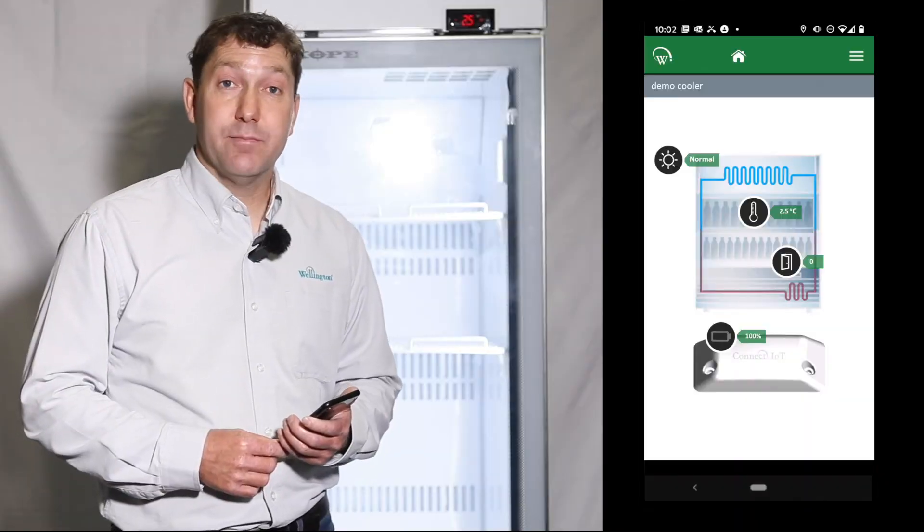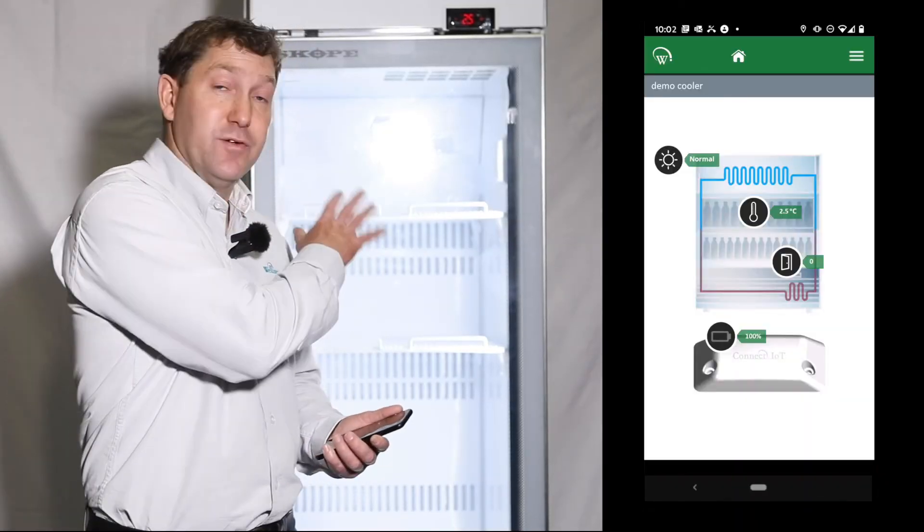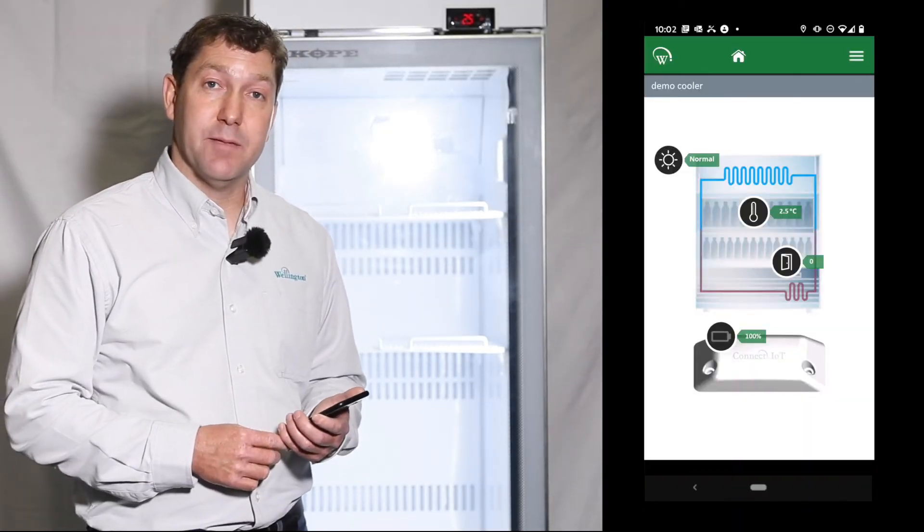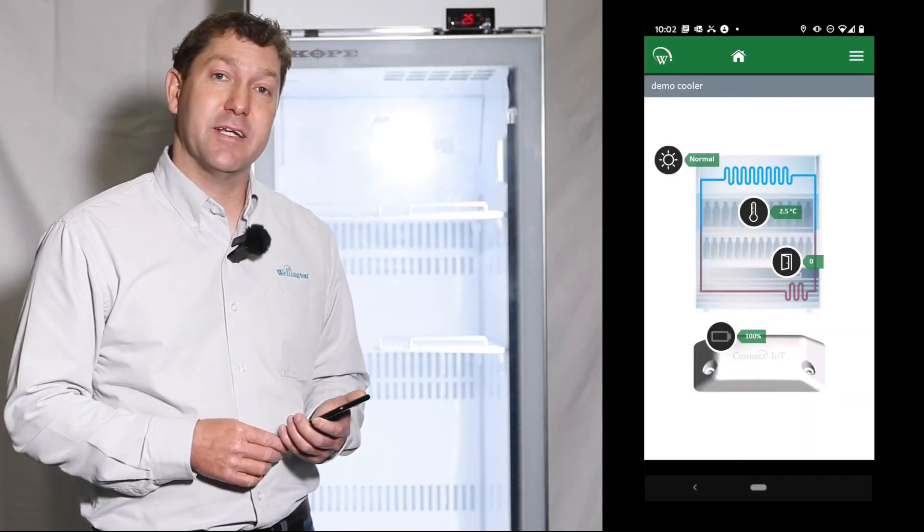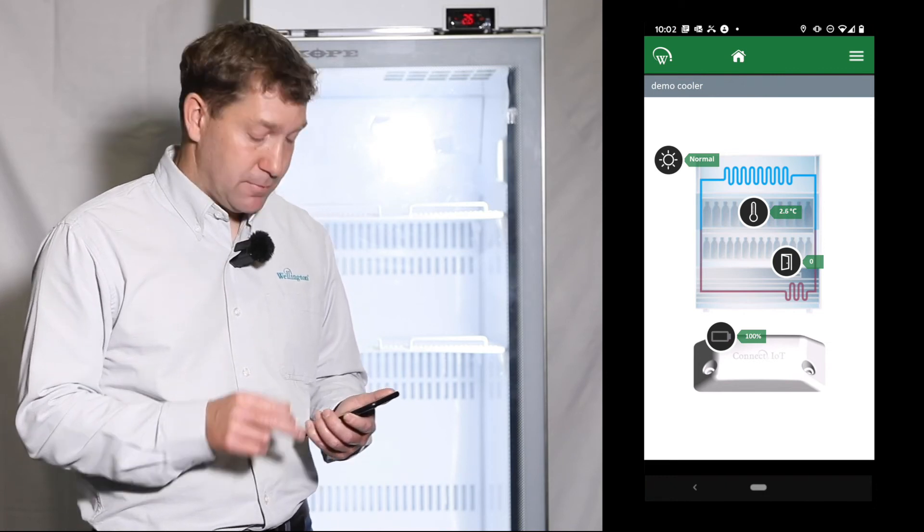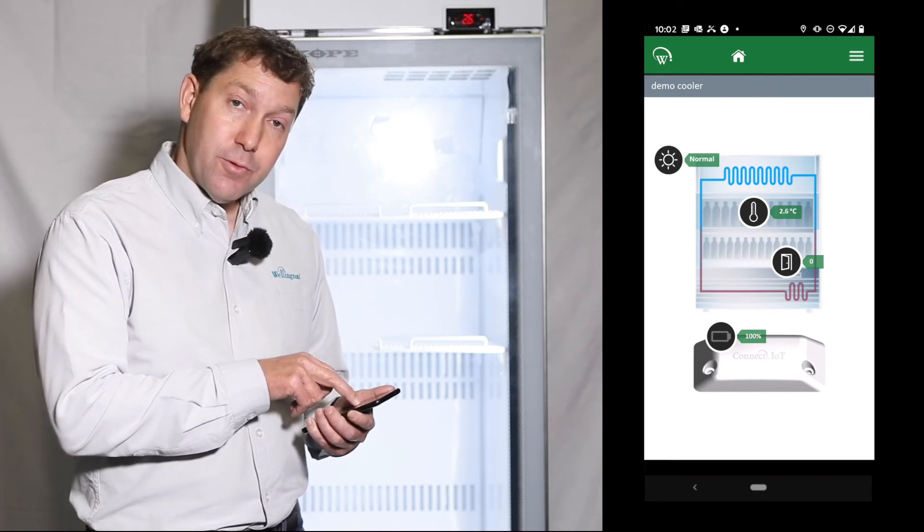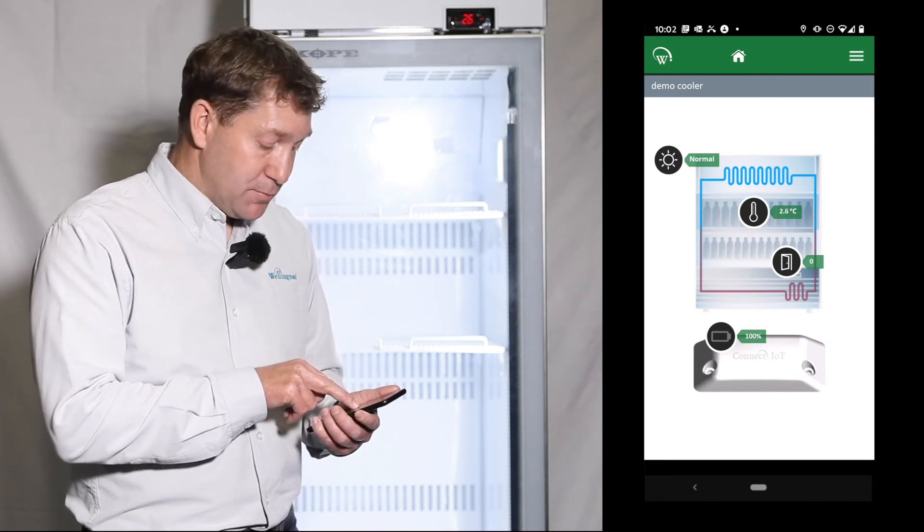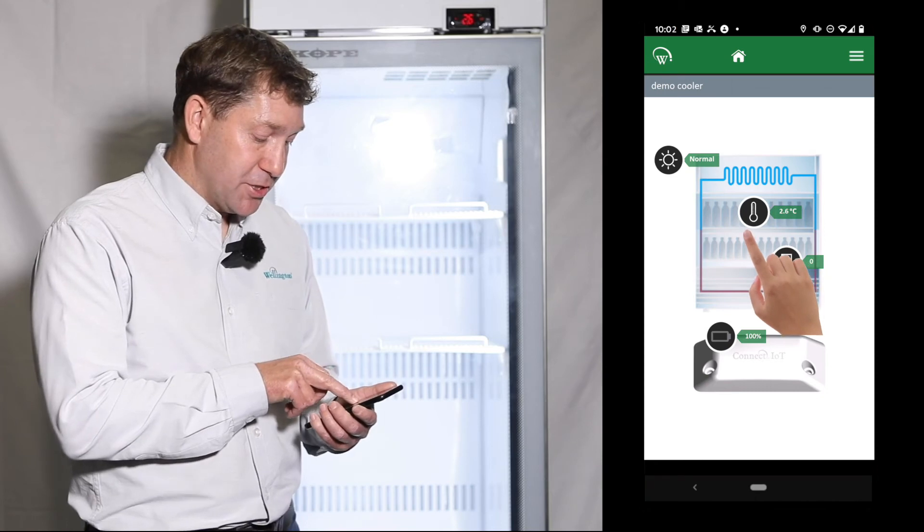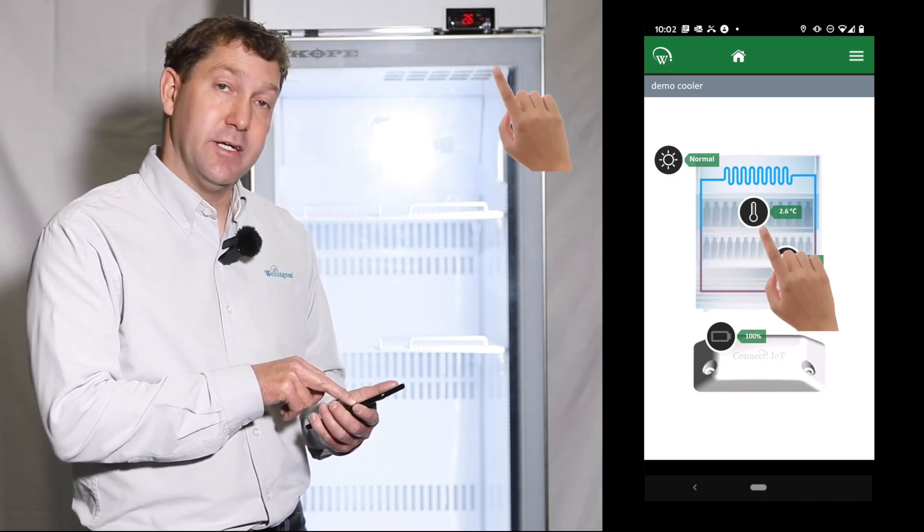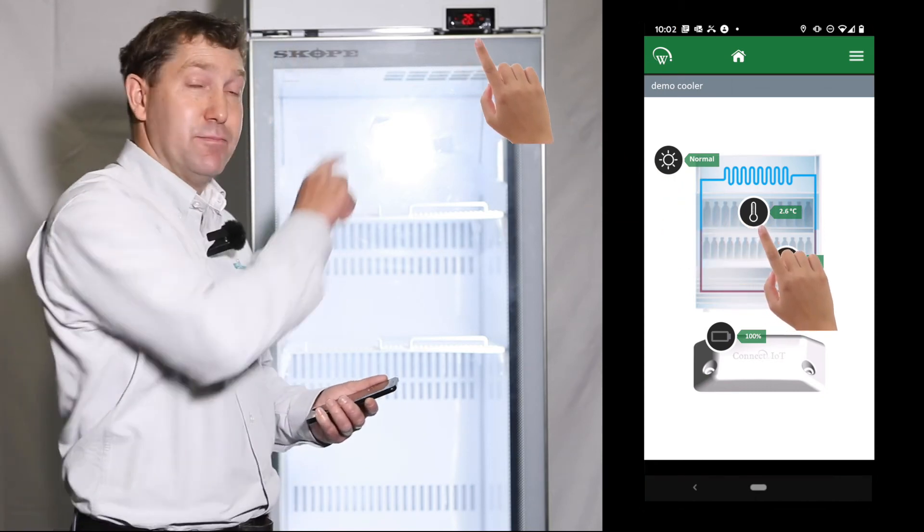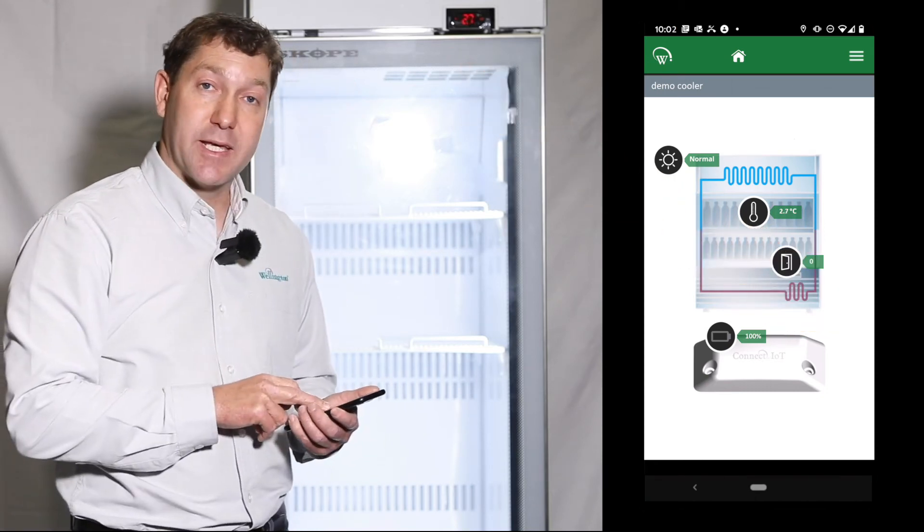Now that the Connect monitor has been fully installed and we've done the setup, we're just going to validate that the sensor readings are correct. When I navigate to the home screen, as you can see, the temperature that is shown on the field app matches the temperature at the top of the cabinet.